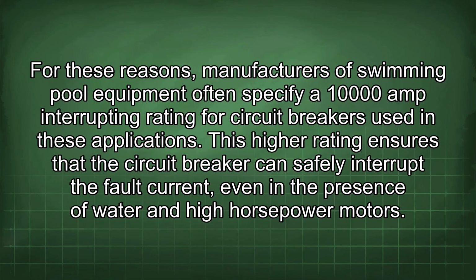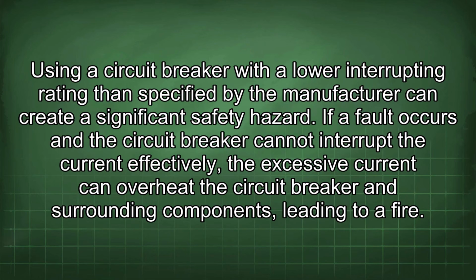For these reasons, manufacturers of swimming pool equipment often specify a 10,000 amp interrupting rating for circuit breakers used in these applications. This higher rating ensures that the circuit breaker can safely interrupt the fault current even in the presence of water and high horsepower motors. Using a circuit breaker with a lower interrupting rating than specified by the manufacturer can create a significant safety hazard.